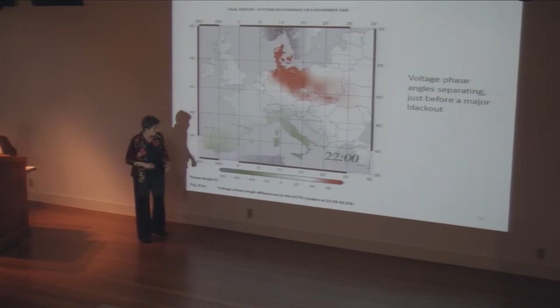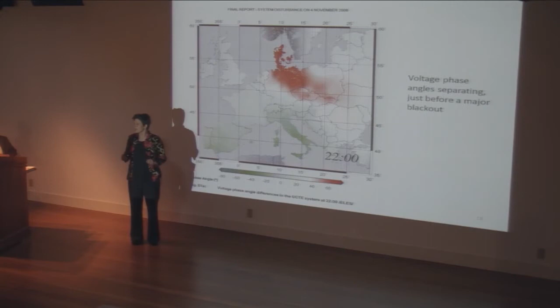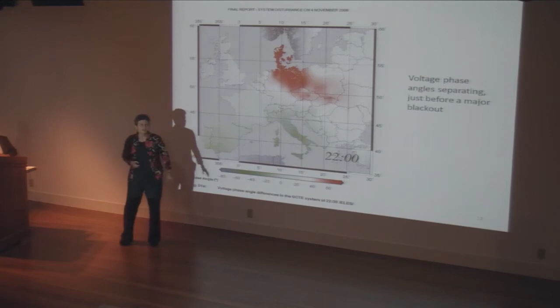It looks like the wind was kicking up in northern Germany and Denmark. They actually would have liked to shut some of those turbines off, but didn't have a way to communicate quickly enough to reduce the power generated, whereas in southern Europe there was more power being imported, so there was a lot of power flowing from north to south. They had lost a couple of transmission links, so there was a big impedance between north and south. As a result, the angles pulled apart by tens of degrees to where the system would have become completely unstable, had there not been relays that opened and said this is too far, we're separating. Essentially, the European grid separated into different chunks, and some load was lost. This was not a good day.